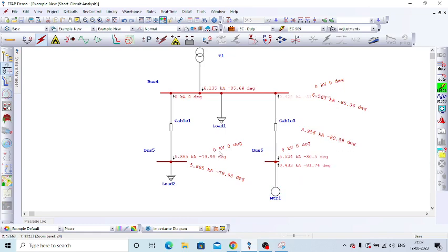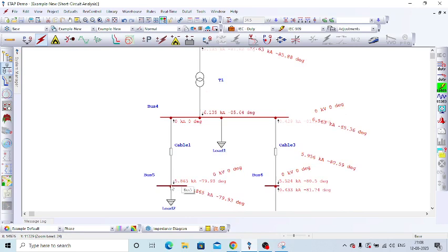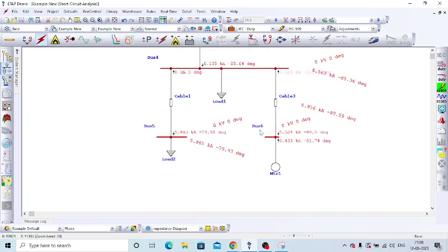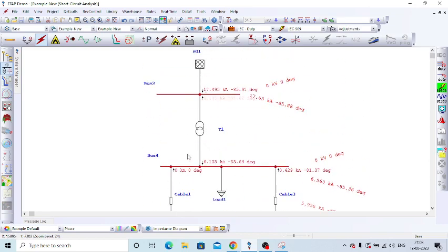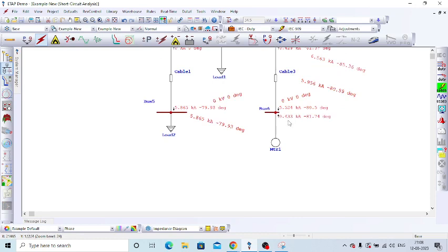Here you can see in this bus the maximum fault current, that is 5.865, coming from the grid source to this fault point, bus 5. But in bus number 6, 5.524 kiloampere fault current is coming from the grid source to the fault point, and 0.433 kiloampere of fault current is contributed by this induction motor. Because the induction motor has inertia, at the time of fault the motor will deliver some amount of fault current. Right.